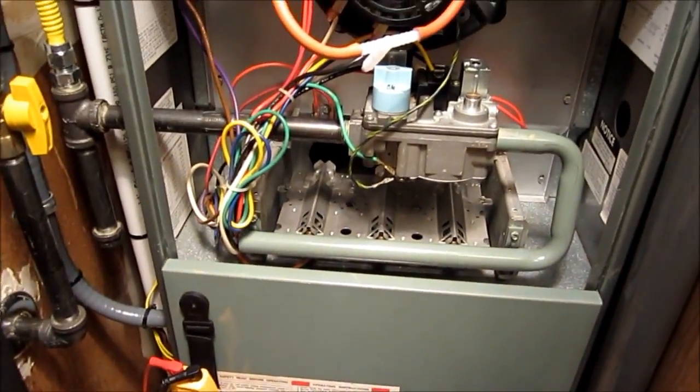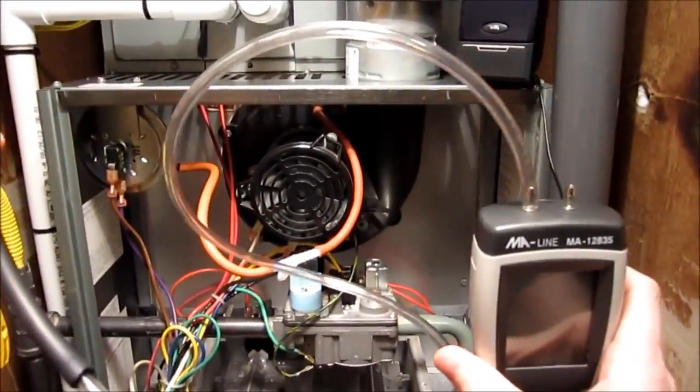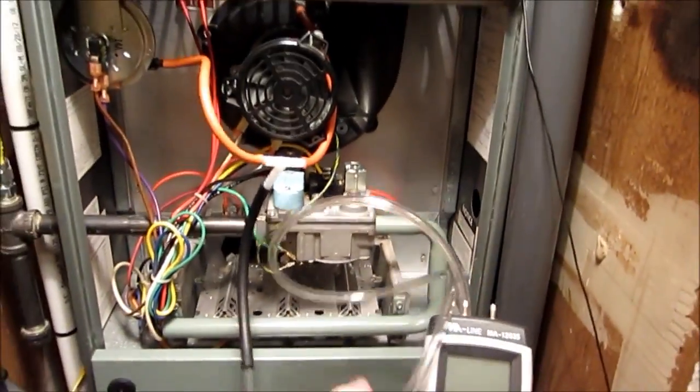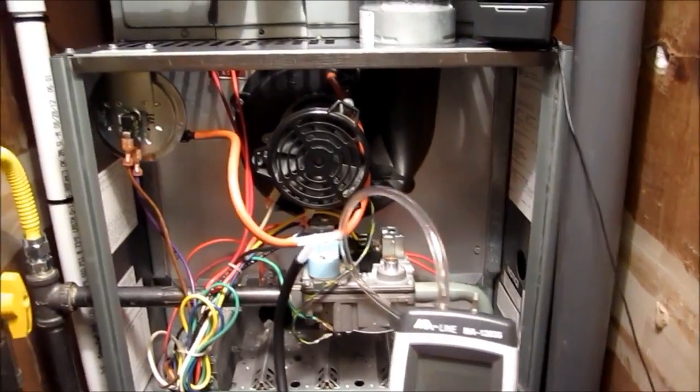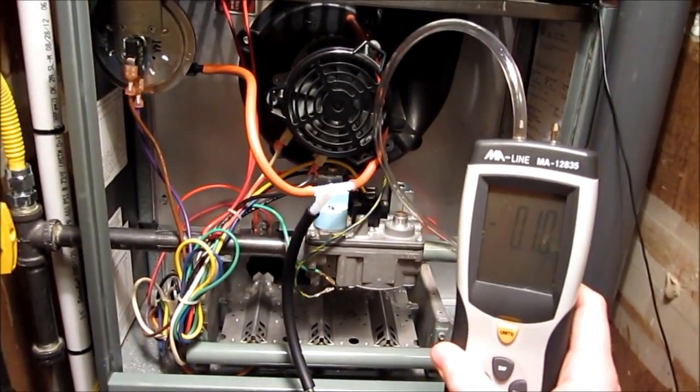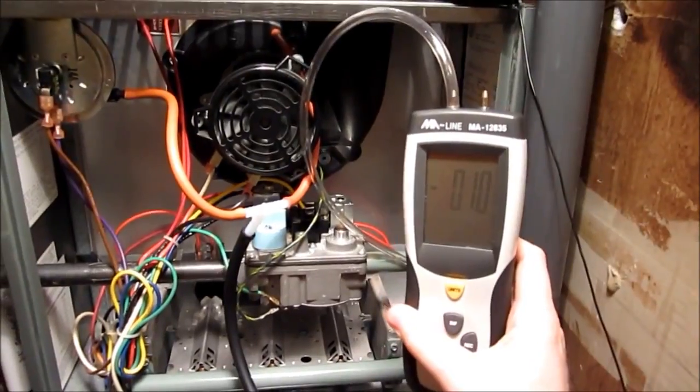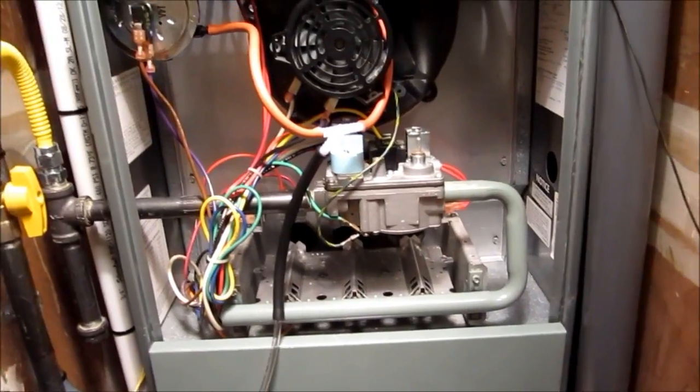Now I bet you got something coming off your new MA-Line manometer there, don't you? Yeah, I've got two different hoses to make it fit right, but it works. Okay, I got the manometer connected. All right, perfect. Now hook the manometer to the negative side. Yeah, it's hooked to the negative side. I do have a MA-Line too and I know it's on the left. What did we say we were looking for, Ray? 0.30 is what the pressure switch is.